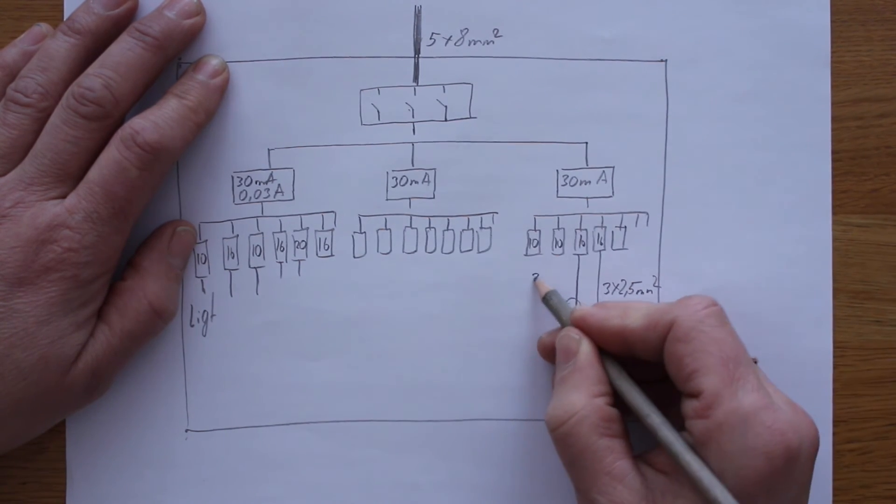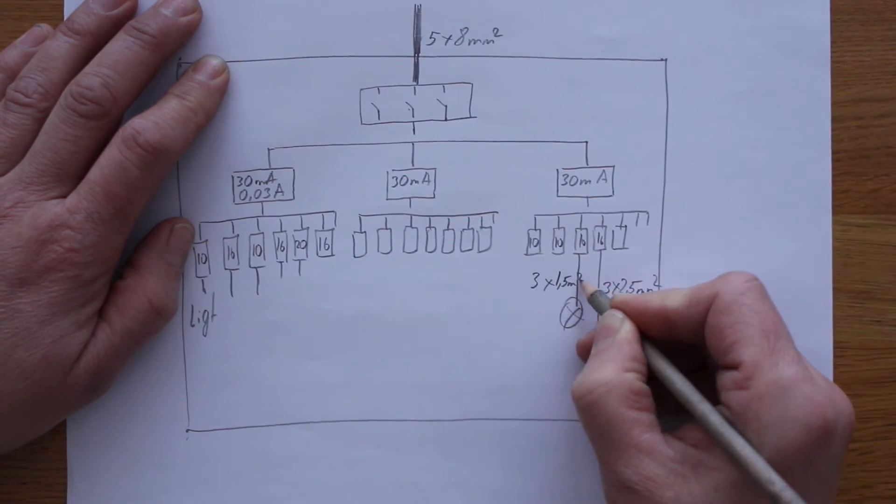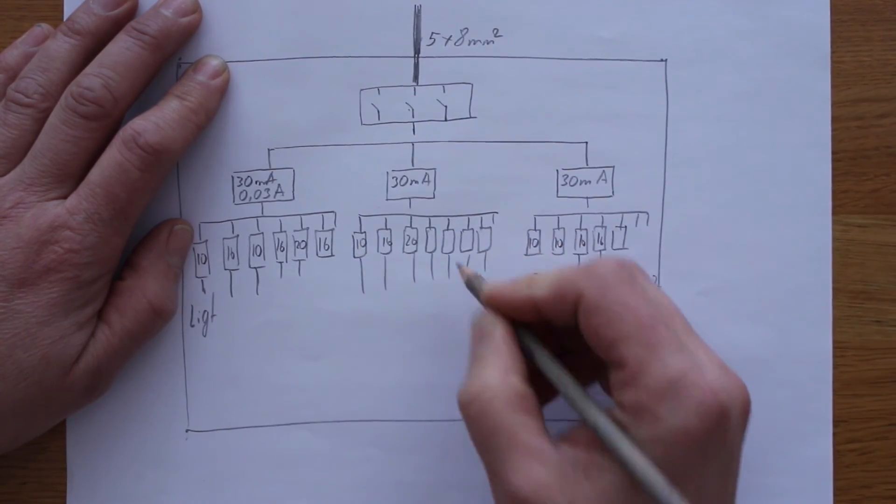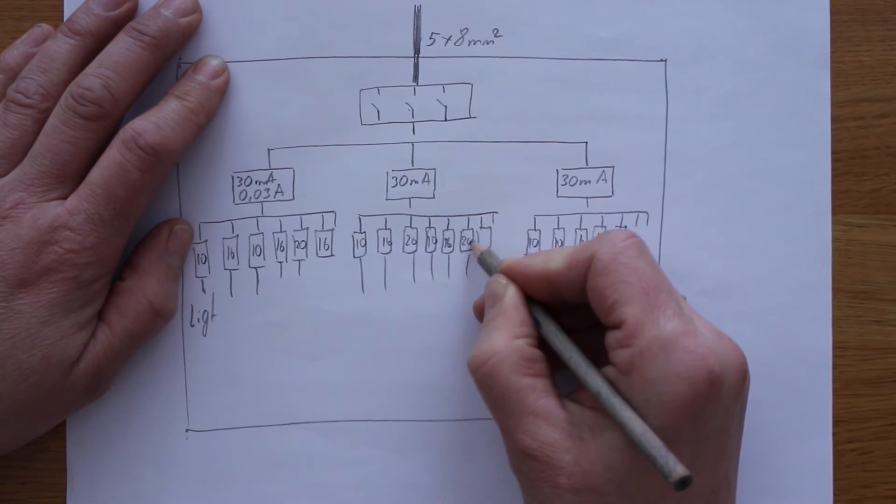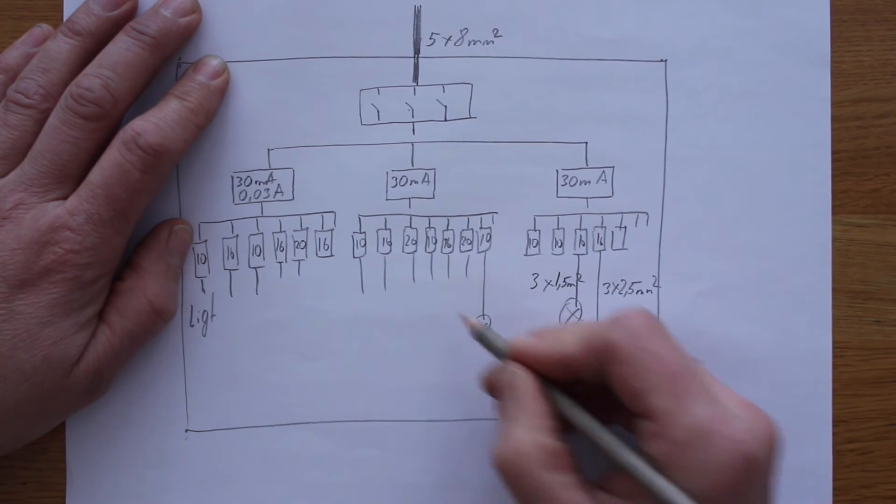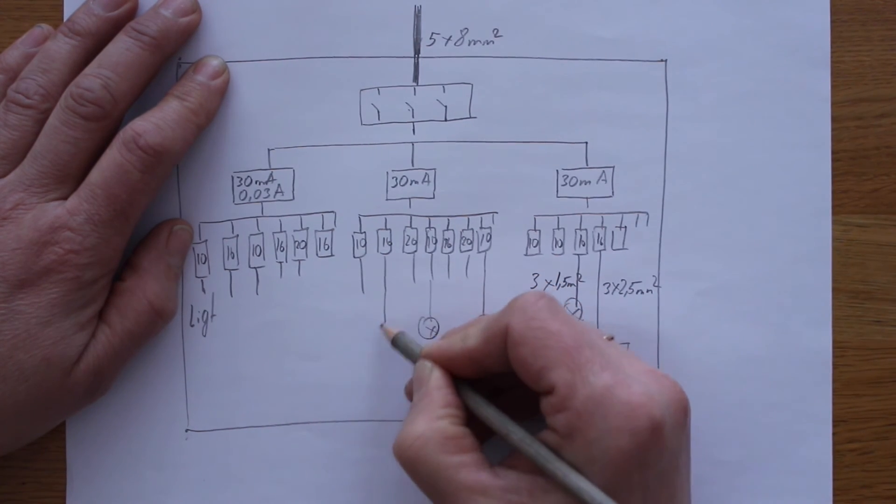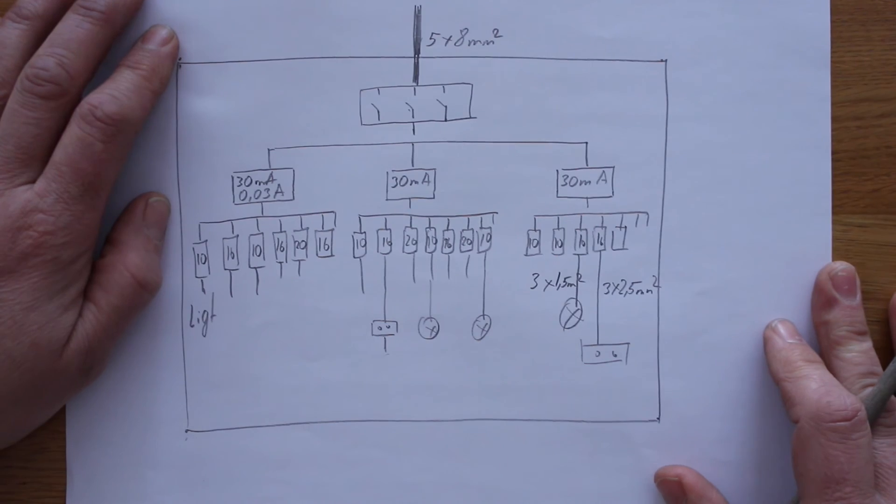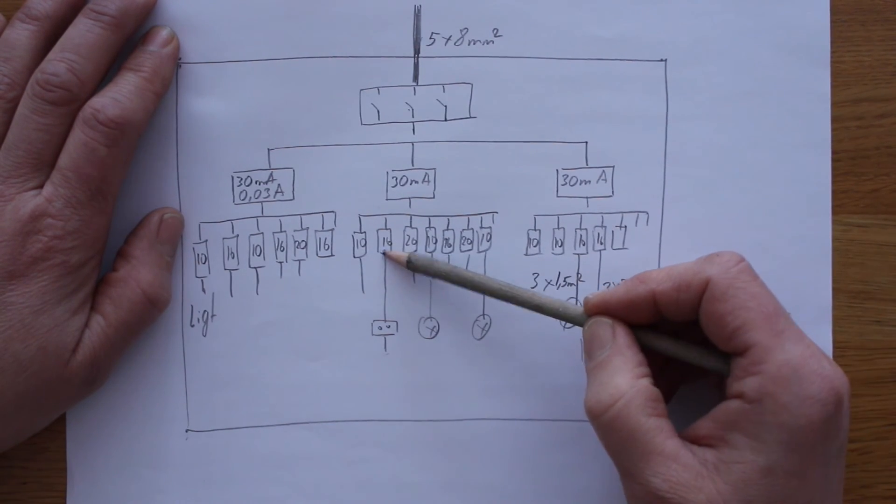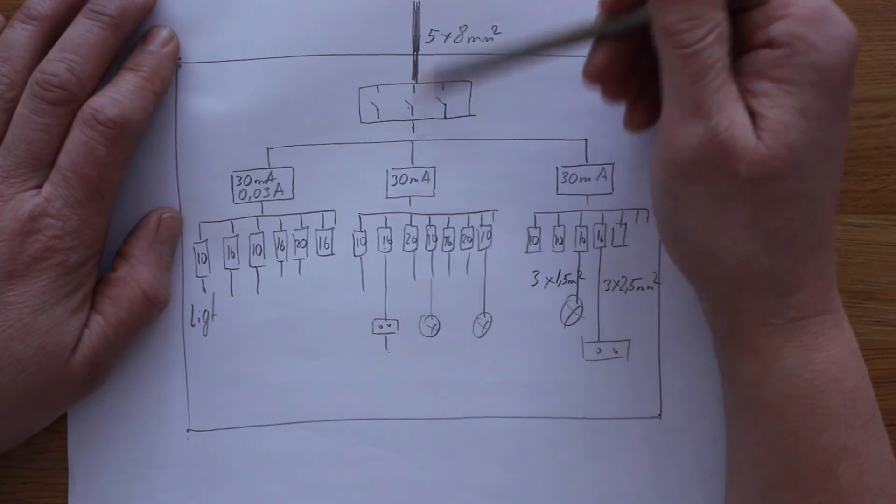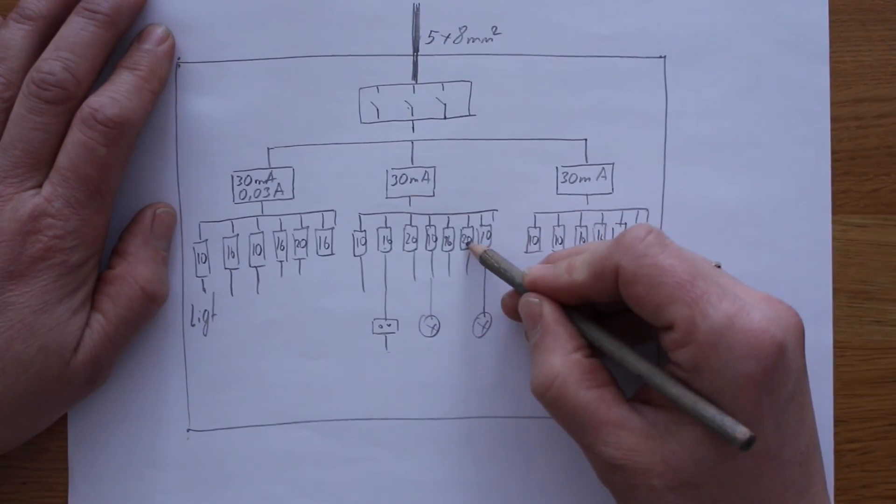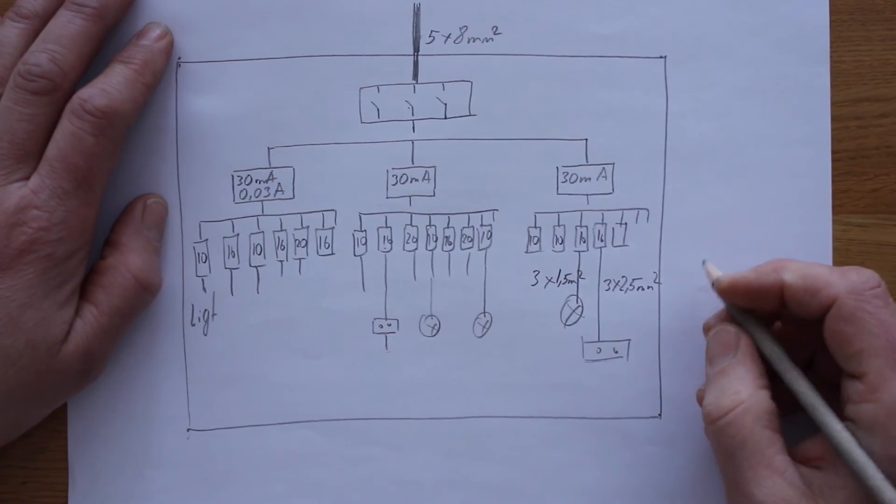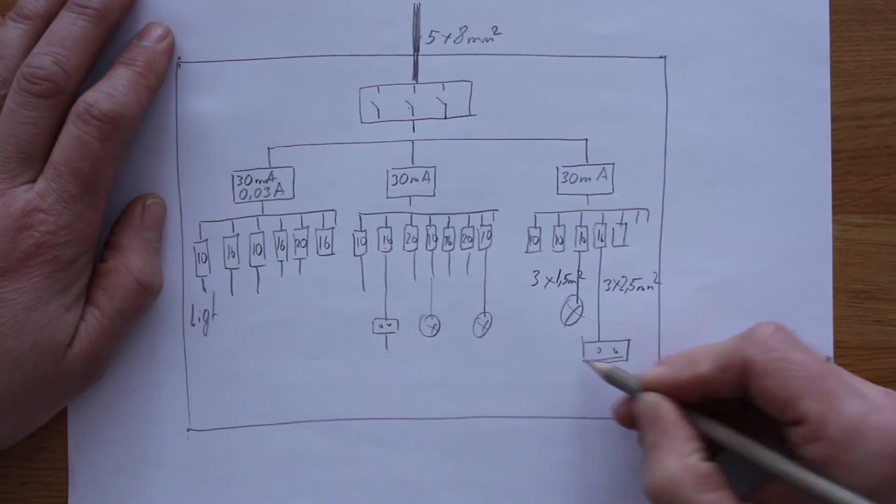By cables, to the socket, 3 by 2.5 millimeters. And to light, cables come 3 by 1.5 millimeters. So about selectivity: if you have here 16, in general distribution you have 20 or 25. If you have here 20, also in general 25. This is selectivity. You need to follow this. Now we look how it looks like in a place.